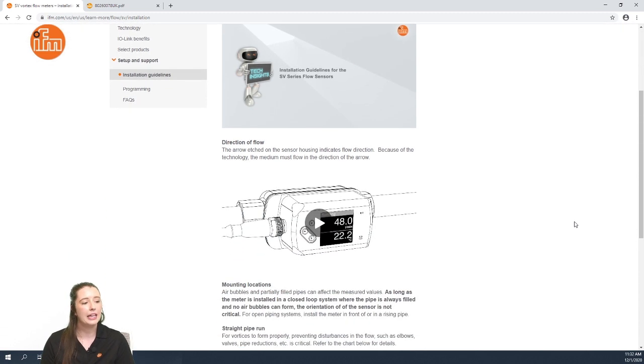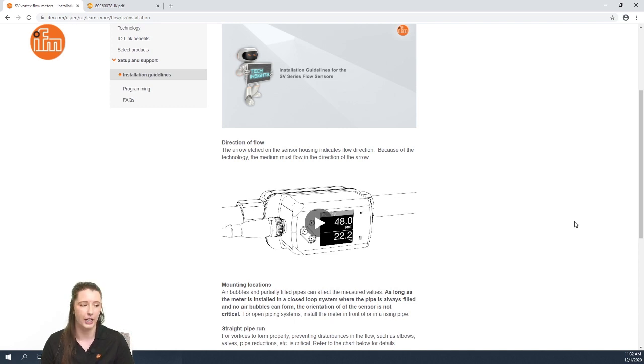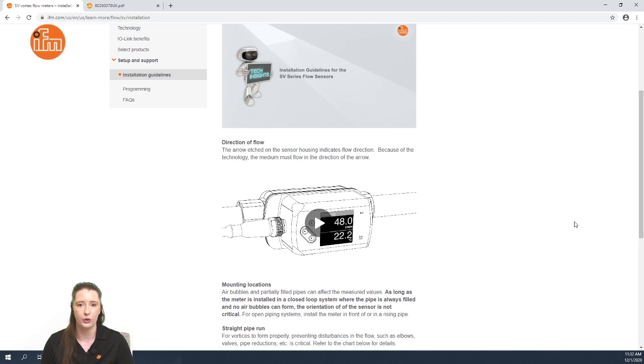So to begin, let's talk about the direction of flow. Because of the vortex flow principle used in these sensors, the direction of flow is important. Therefore we have an arrow etched on the sensor housing itself that indicates the direction the media must flow through the sensor.